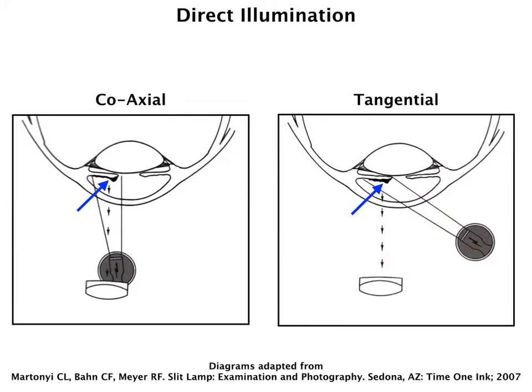Two similar techniques are the coaxial and the tangential. Usually it uses a wide open slit beam or a diffuse light. In the coaxial, the slit beam and the slit lamp are lined up, whereas in the tangential, the slit beam is at a very large angle in relation to the slit lamp. This helps to contrast skin lesions, iris lesions, cysts, or just a normal iris.